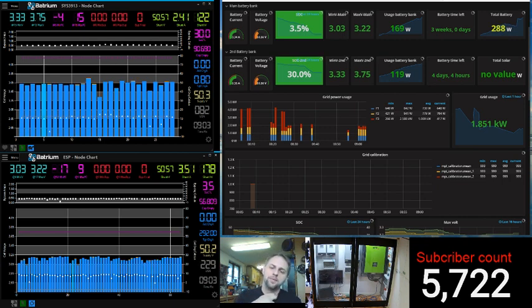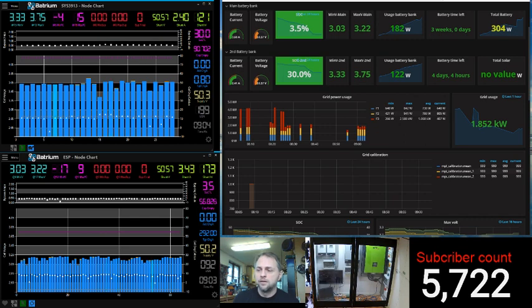What's important about the UPS stuff is that not all of them are even close to made for charging lithium ion. Some of them you can set the bulk and float charge voltages, and by doing that you could get it to work. Other than that, it's important to also understand that the smaller UPS systems are not made for 100% runtime. Some of them even state that you are not allowed to put a bigger battery than a certain number of amp hours on it, and that's because you may overload them.